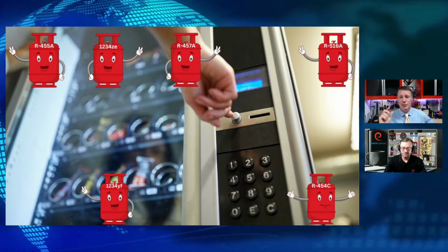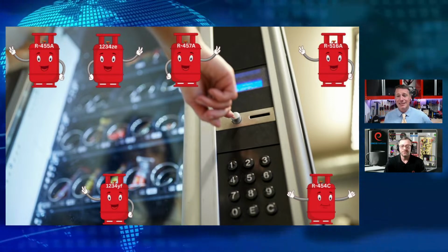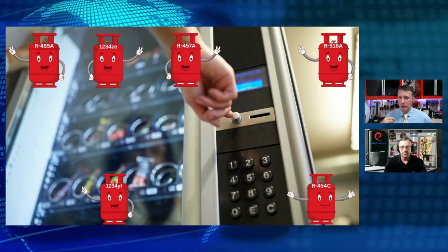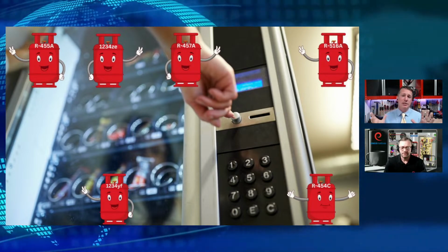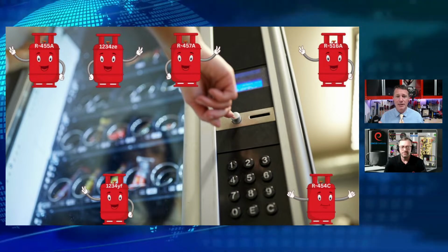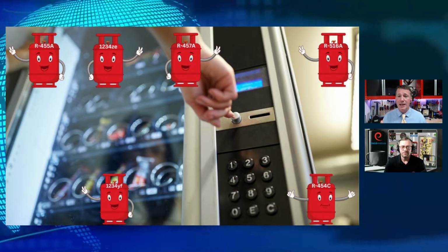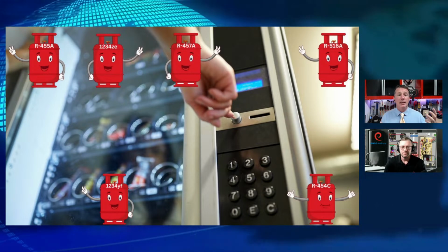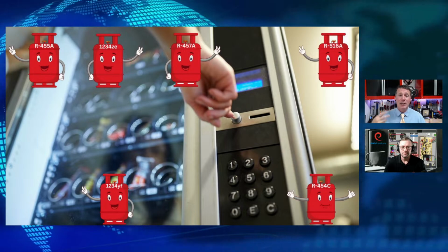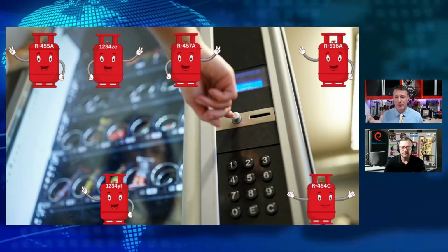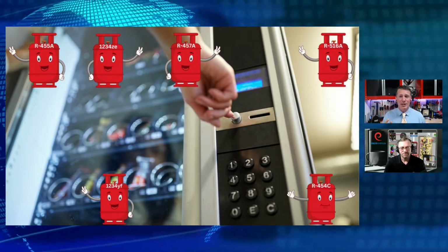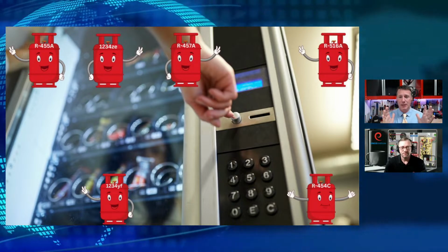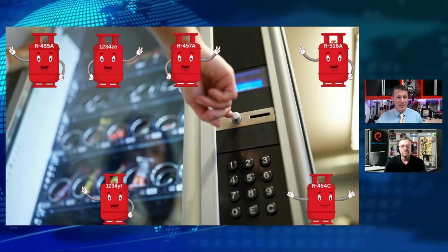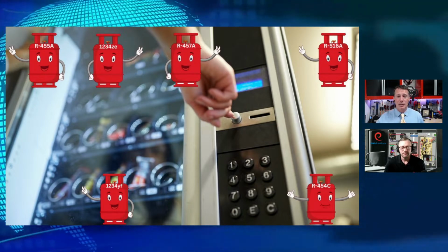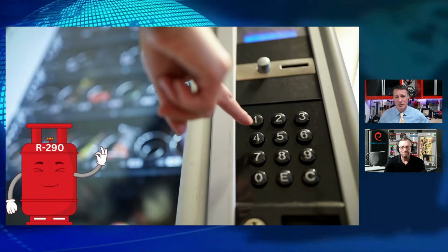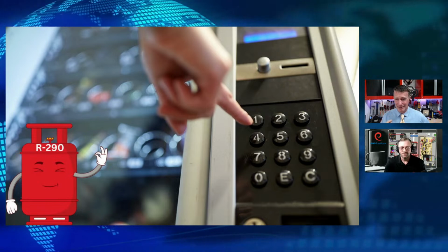Well, we're really going to have two different classes of equipment based on the application and the installation area and your local building codes. So if we talk about equipment that falls into that A2L classification, right? We can utilize refrigerants like 1234YF. We could talk about 454C. We've still got that 1234ZE as a candidate. And then we got our 455, our 457, and our 516A. But we also have the ability to have a similar cabinet, completely different refrigerant, right? We have the ability to now build a piece of equipment, same construction, maybe different application, and utilize R290.